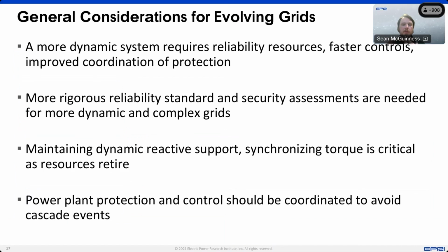So really, to wrap up and summarize the general considerations for these evolving grids: grids everywhere are becoming more complex. There's greater variability and greater uncertainty, and as your resource mix changes, it's vitally important to consider the dynamic system. These dynamic systems require reliability from their resources, and in some cases that may mean faster controls. It also means we need improved coordination of protection. So not just transmission line protection, but our voltage protection, frequency protection, rate of change of frequency, and so on, to ensure that in response to an event we get controlled tripping and can bring the system back into normal operating ranges, and that we don't initiate a cascade tripping of multiple power plants.